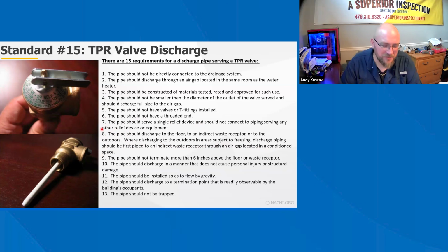So we did a large apartment complex, a 40-some door multifamily complex, and inevitably, just through the nature of apartment complexes, you're going to have a range of ages of equipment installed. A lot of times when a tenant has a problem, they don't notify the landlord or the manager. So we were doing the inspections, and it was wintertime, I think it was December, and we found four frozen TPR valves on the outside of the apartments.